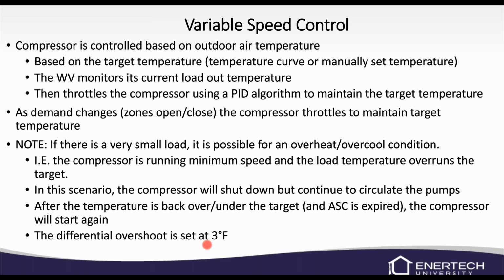Now, we talked about the 5-degree temperature difference. We do have a little bit of wiggle room there of 3 degrees. So we can overshoot a little bit or undershoot, and we're still okay. It'll stop a little bit of the cycling, but if we do overshoot or undershoot, it will shut off the compressor until it's back within range.